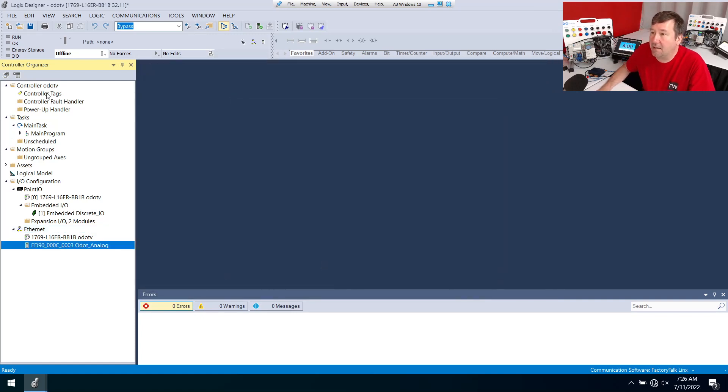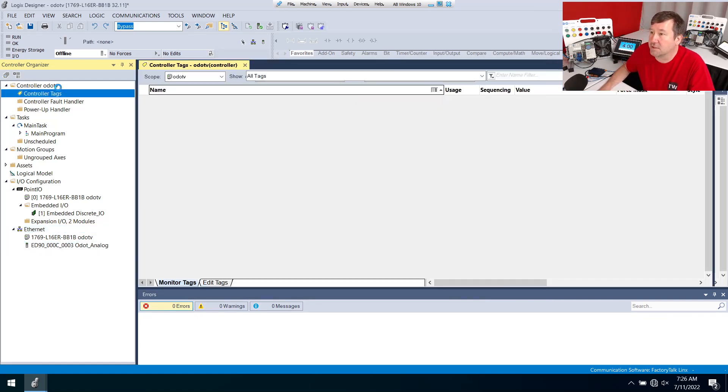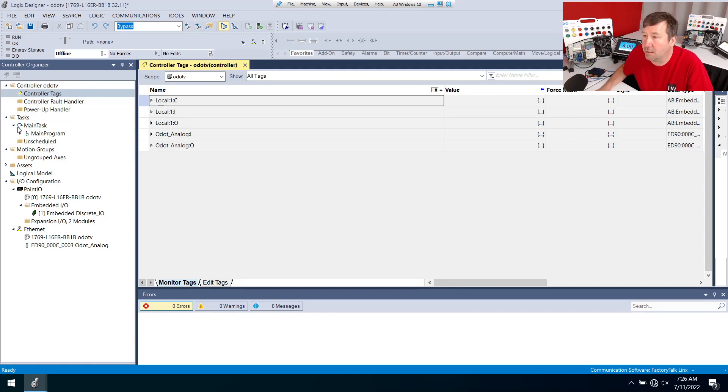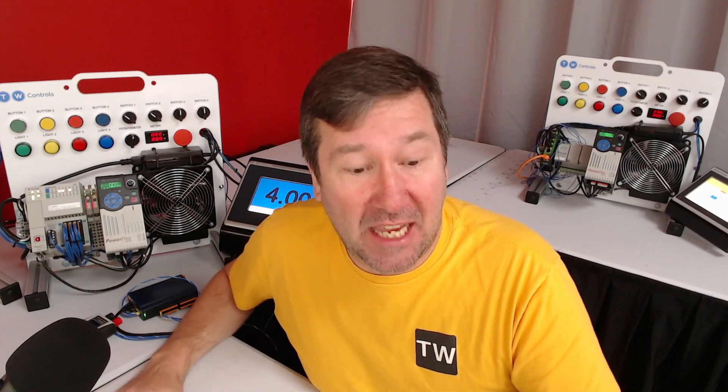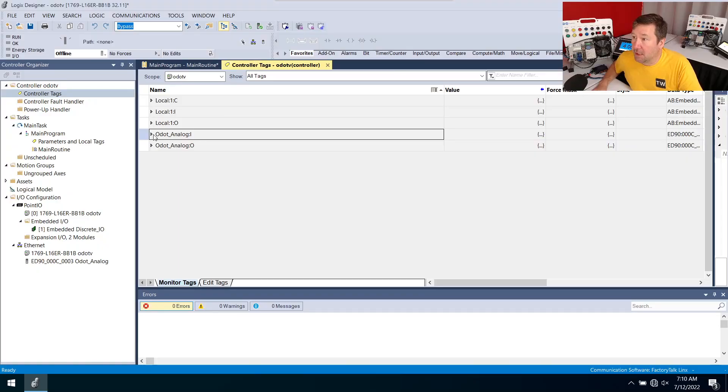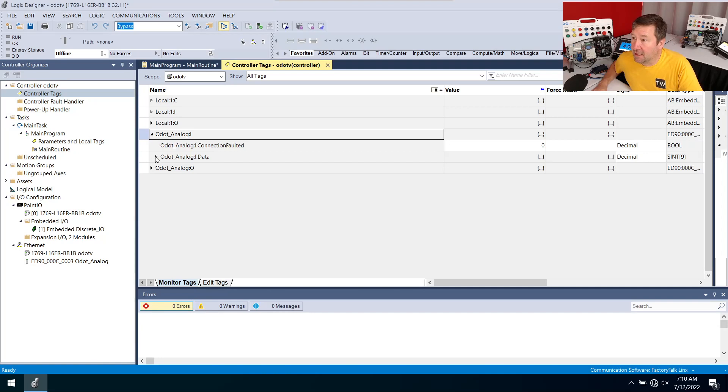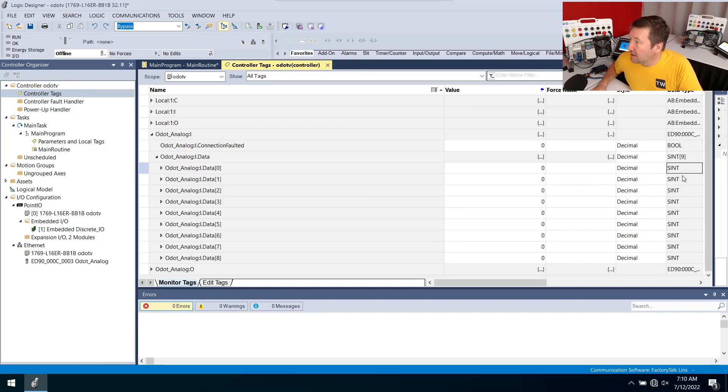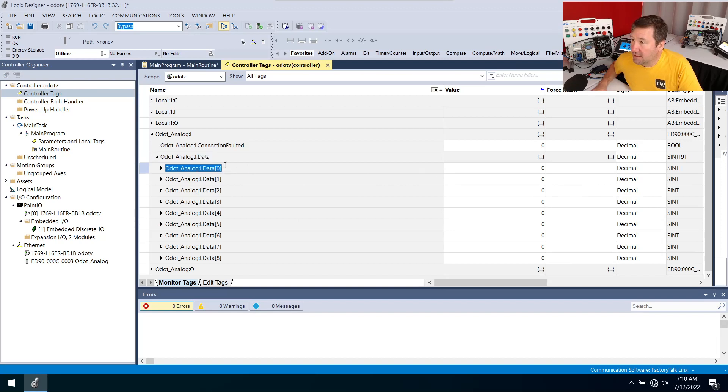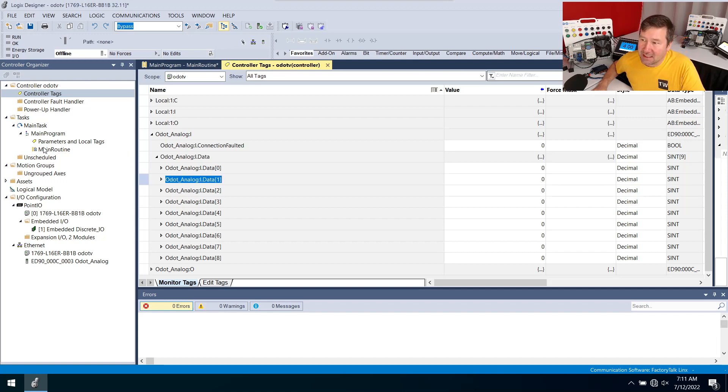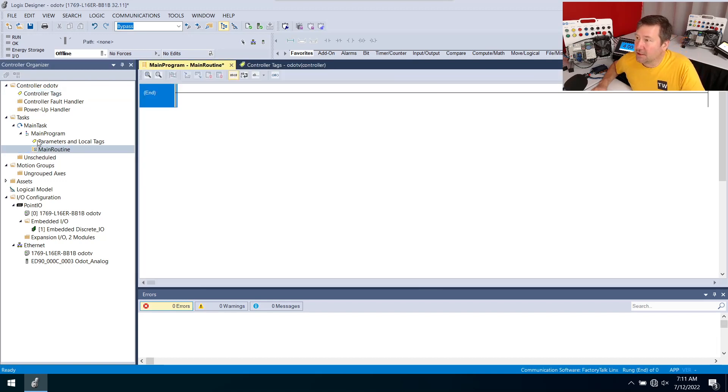Now if we go to controller tags we're going to have ODOT analog colon I and ODOT analog colon O. Yes I had a wardrobe change, I'm running a class this week. But now that we have that we're going to need to do some scaling to it. If we open up the ODOT analog colon I and then open up the data you see that they're in single integers and our first analog value is actually in zero and one so we're going to need to combine them. That's actually a lot easier than you would expect.